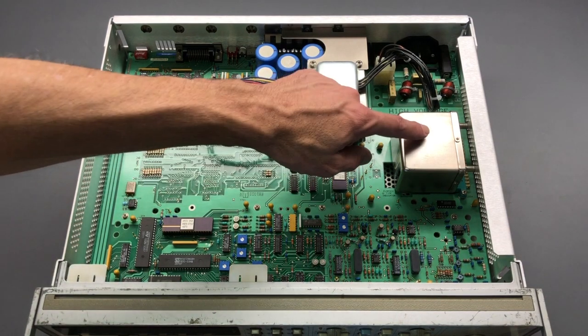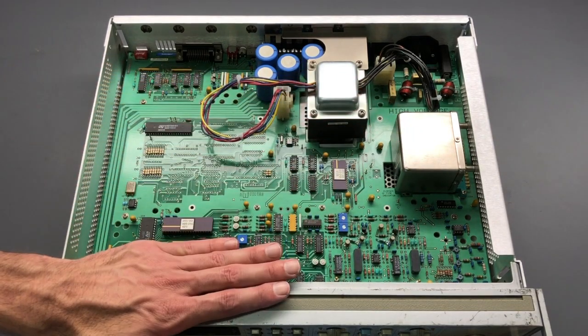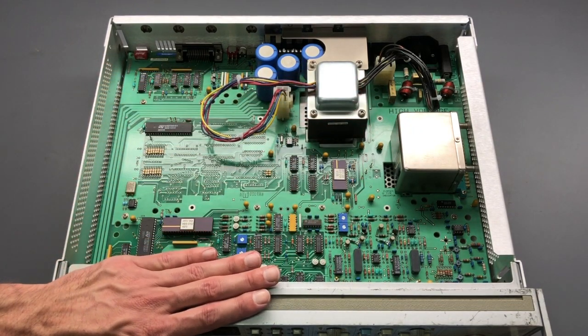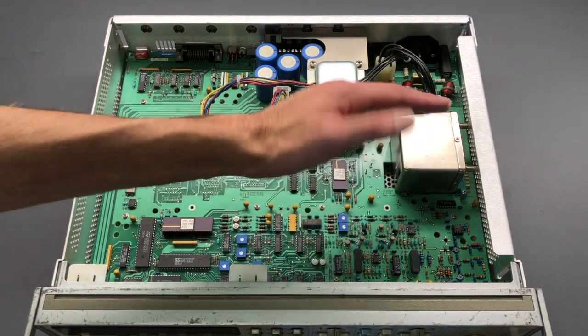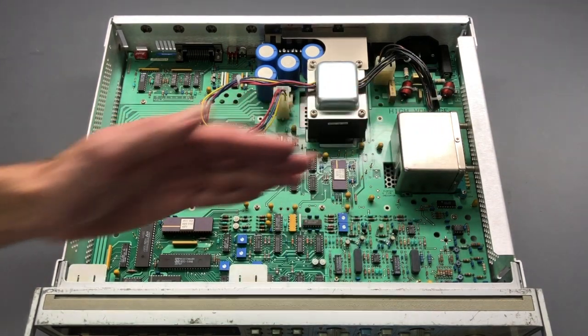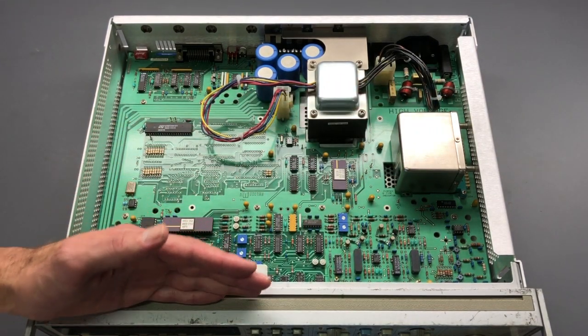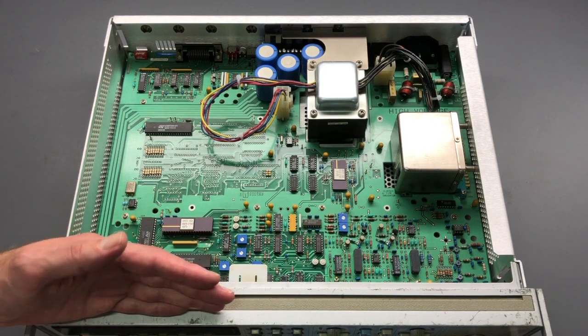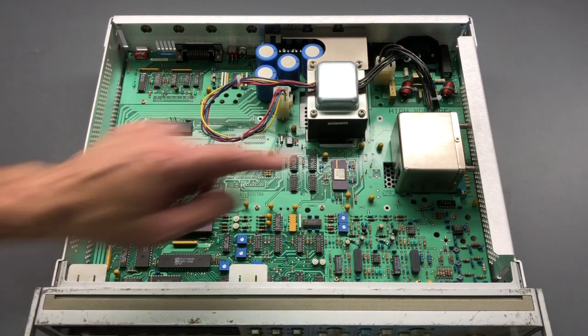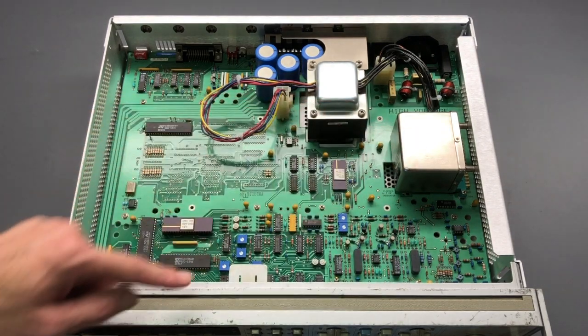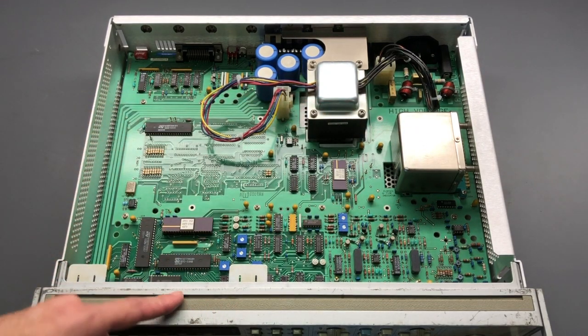However, the time base oscillator in a frequency counter needs to be very, very accurate, and the less drift it has and the more stable it is, the more stable and the more accurate the frequency will be on the readout on the frequency counter. So when this oscillator drifts a little bit, there's an error or a drift in the displayed frequency.